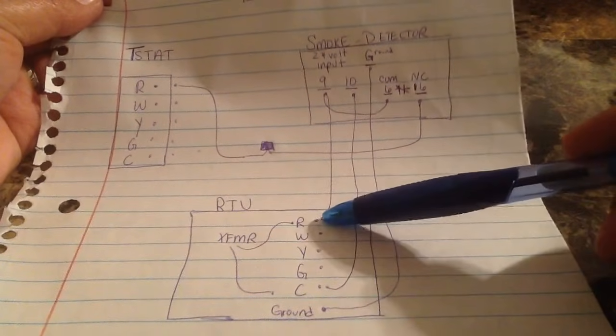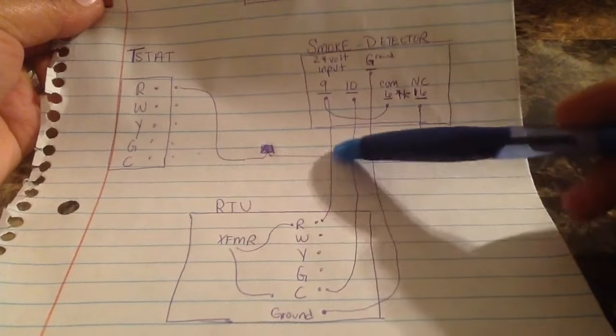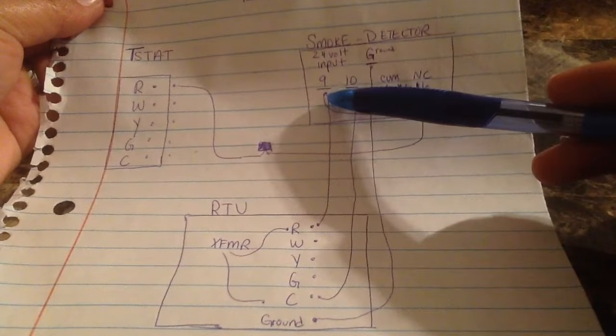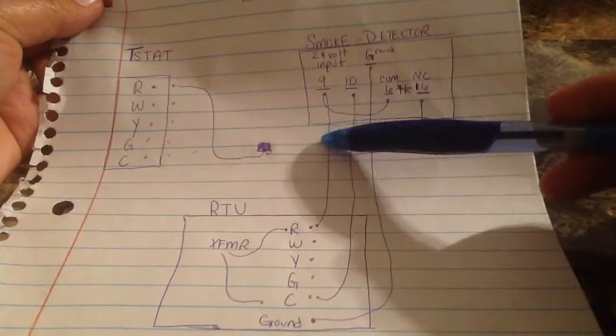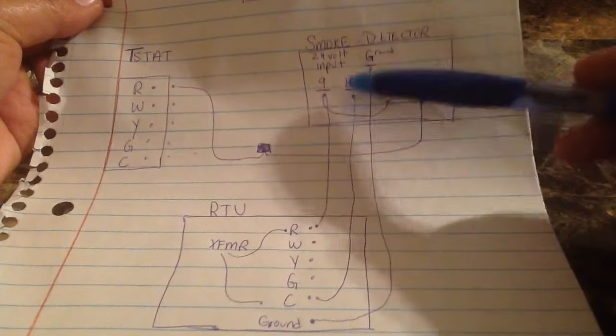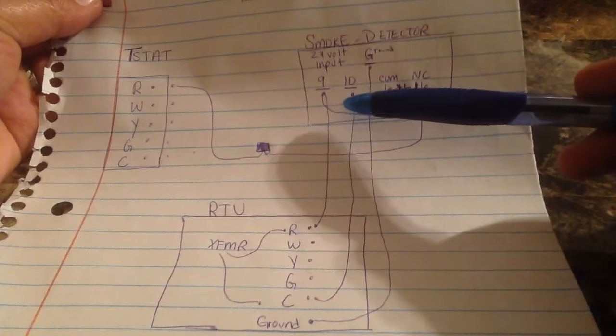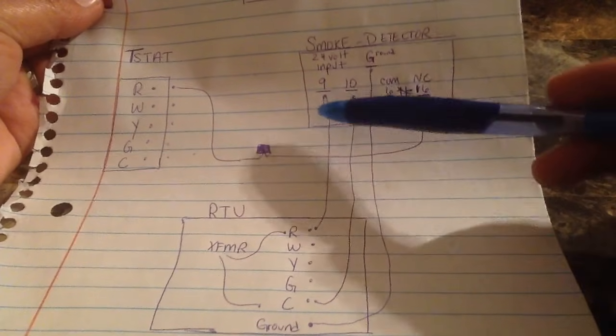So to kind of summarize it here, we're following the 24 volt circuit. We're going 24 volt coming out the transformer directly powering it up, so current is going between nine and ten powering up the board at all times. It's always hot.